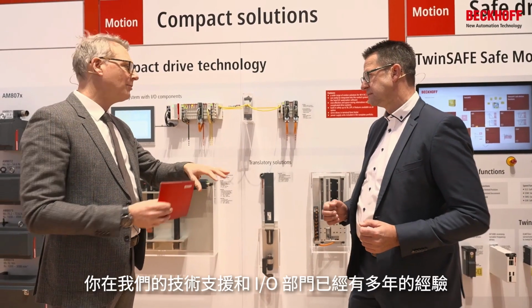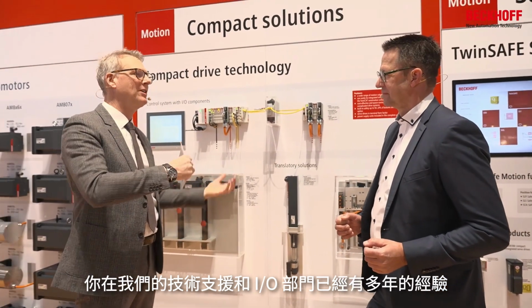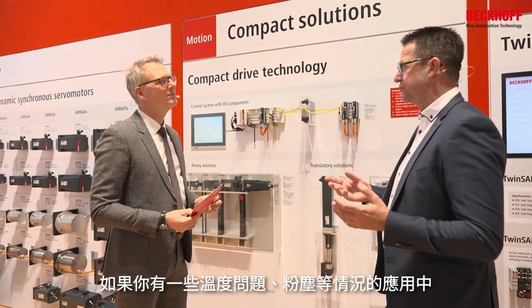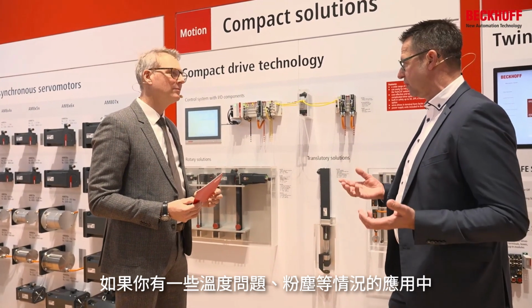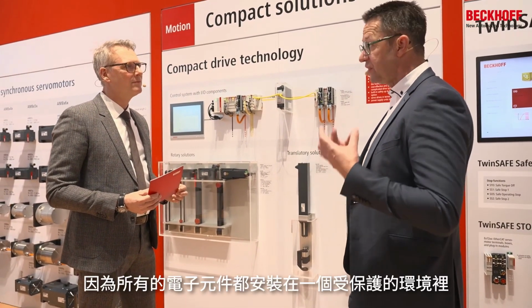Okay, now you have so many years of experience with our support department, our I/O department. Do you have a preference of one or the other? Well, it's not so easy to say because it really 100% depends on the customer application. Of course, if you have some temperature problems, dust in your application and so on, it's better to use a central one because then all these electronic components are in a safe environment, so in a central switch cabinet, mostly air conditioned. On the opposite, if you're using this decentralized solution, the motor electronic is directly at the motor. So less cabling, more modular, really flexible if you want to change something in the plant.